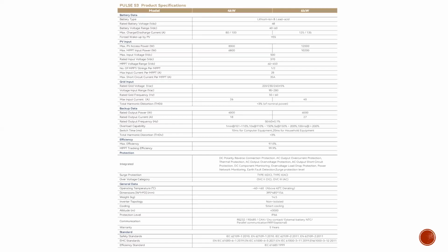And of course, it has AC output overcurrent protection. So we have AC output overvoltage protection. What that is saying is that in case of overload, the inverter is well protected to preserve itself from the damage that overload can cause to the system. Thermal protection. This is an IP66 system, which is designed to be outside. It is so well protected against high temperature that, I'm talking from experience now, as high as about 65, 70 degrees Celsius, we have seen this system working perfectly fine with just about 5% derating. This is from experience, and we have evidence to back it up.